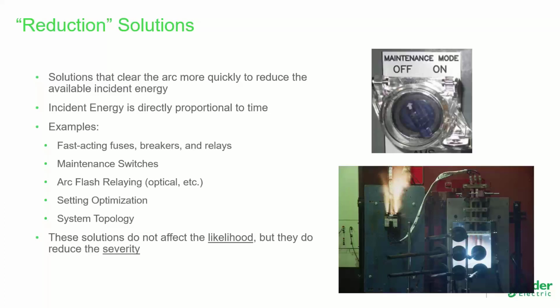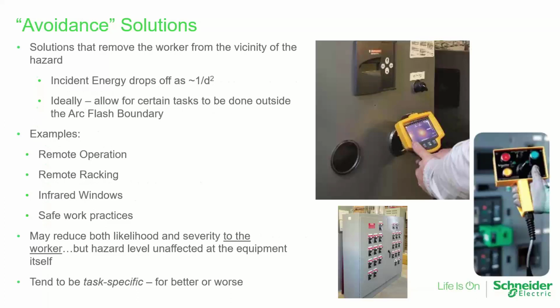The last bullet there is kind of unlike the prevention solutions, which as we said affect the likelihood of occurrence. These tend to affect the severity of the event. We can reduce the calories, but if we're in maintenance mode off versus maintenance mode on, if you're in there in a motor control center bucket taking voltage measurements, you're no more or less likely to create an arc flash event. So again, kind of two aspects of risk there. Solutions may affect those differently. The third category is what we'll call avoidance solutions, solutions that help us remove workers from the vicinity of the hazard or help eliminate exposure, at least to some extent.